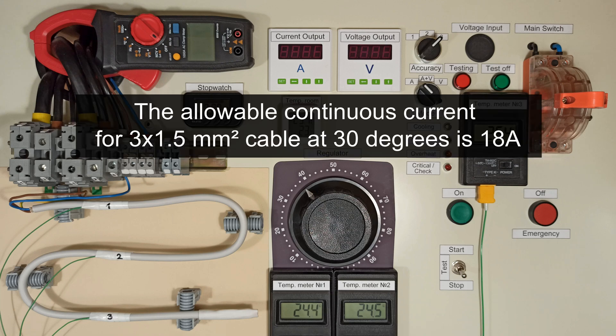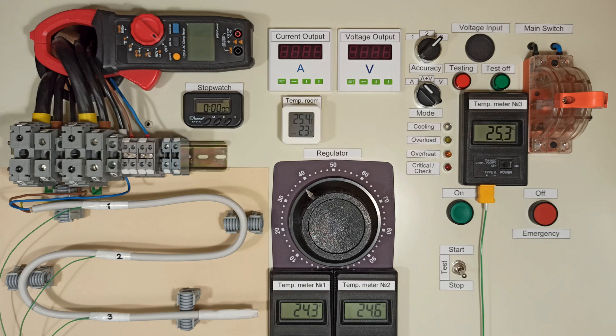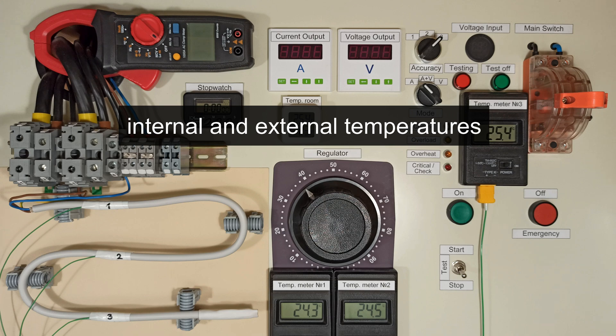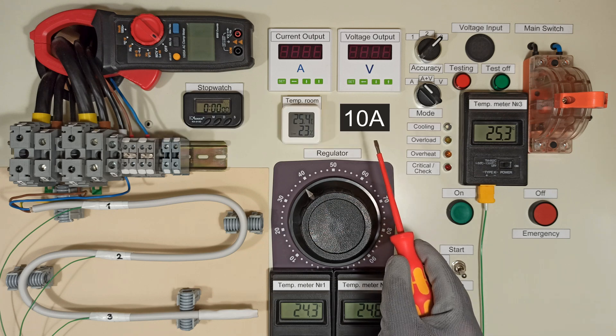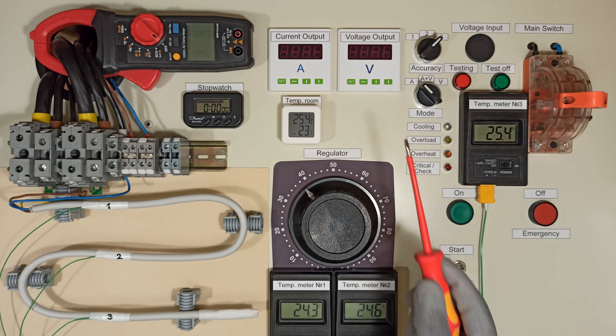The permissible continuous current for 3 by 1.5 mm² cable at 30 degrees is 18 amps. I really want to see what values the internal and external temperatures will reach at 10 and 16 amps. Let's begin.